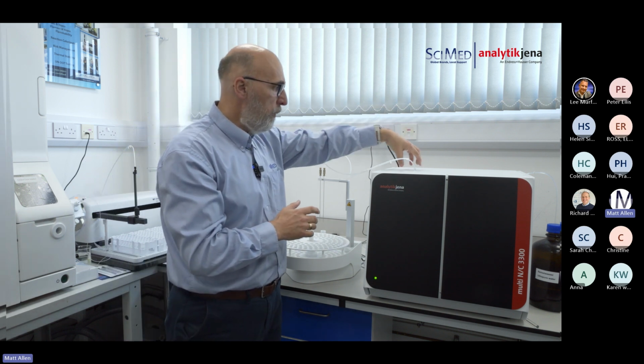And then the direct injection option, the one that sits on top, because we're just filling a syringe, it does use a smaller capacity syringe. So we're working there with typically 50 microliters, again up to a mil, but people are normally injecting about 250 microliters. So there are some various options to consider. But the sample is then injected into the top of the instrument here, and it goes into either the combustion furnace or the UV cell.